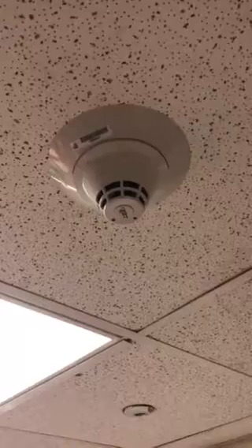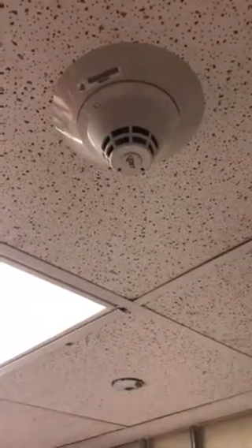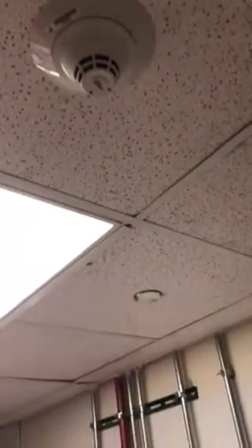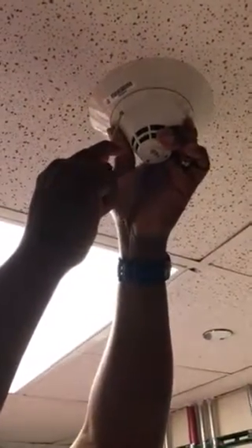When you see that barcode on there, that is not an indication of what the address is. That's for inventory purposes only. So to find the location of this device, we're going to go to the smoke detector, take a pin, your little screwdriver, push this button here, turn it counterclockwise, and it pops out.